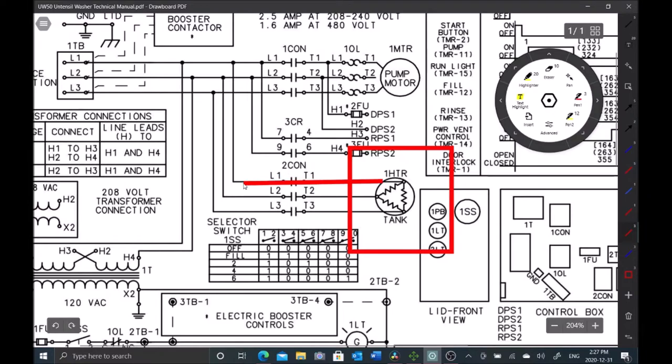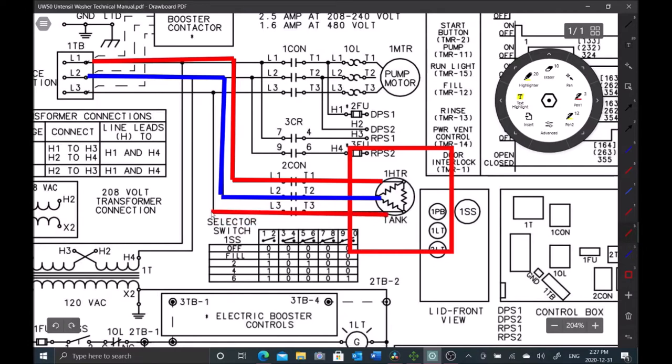We're going to start with our T1 L1. It goes through the contactor contact and it is a straight shot to our terminal block. L2 same thing. We come here, go through our contactor contacts and come right up to L2 on our terminal block.